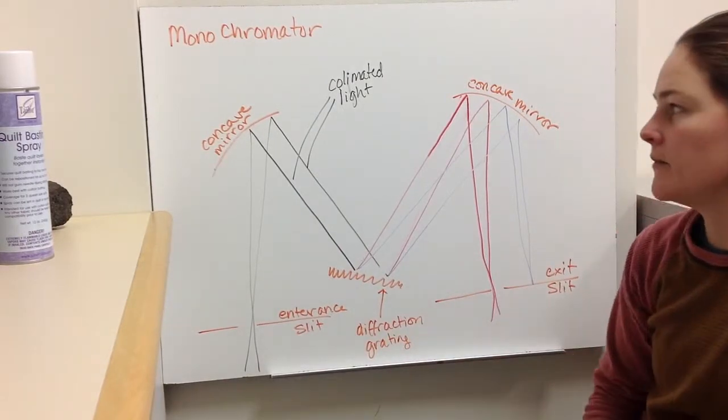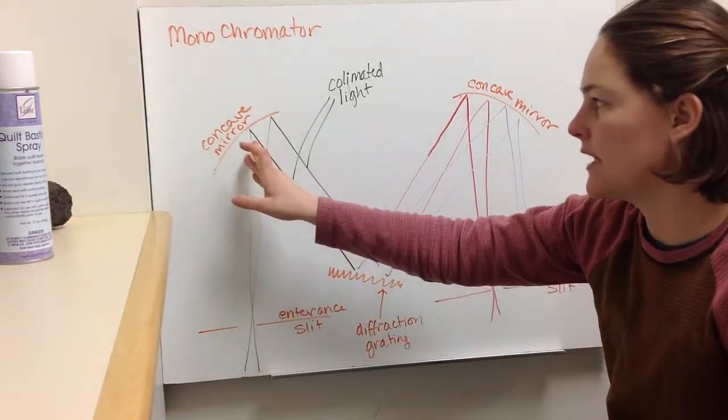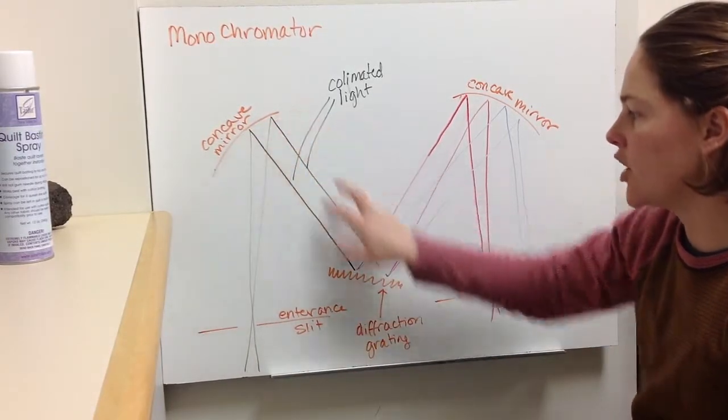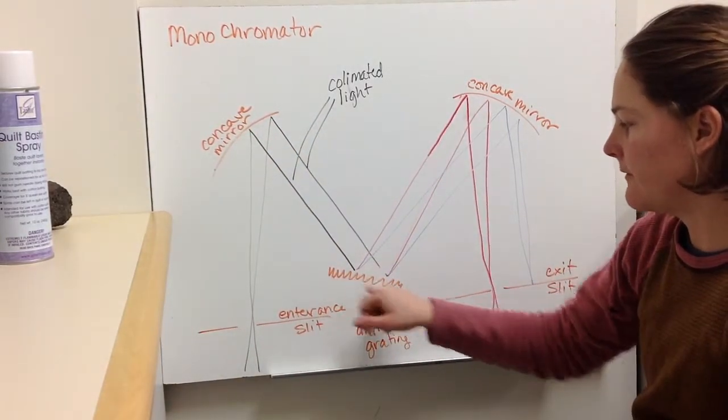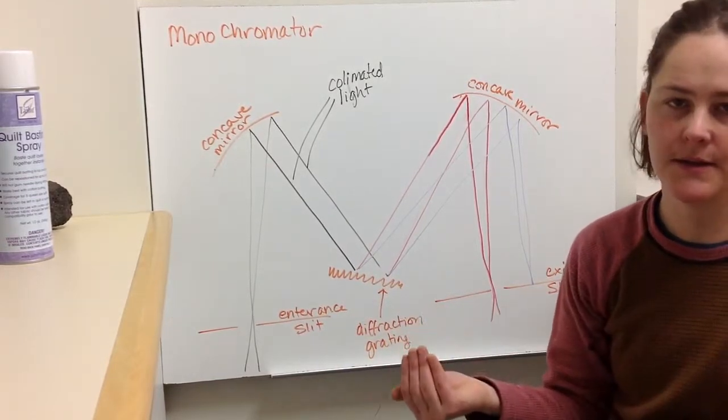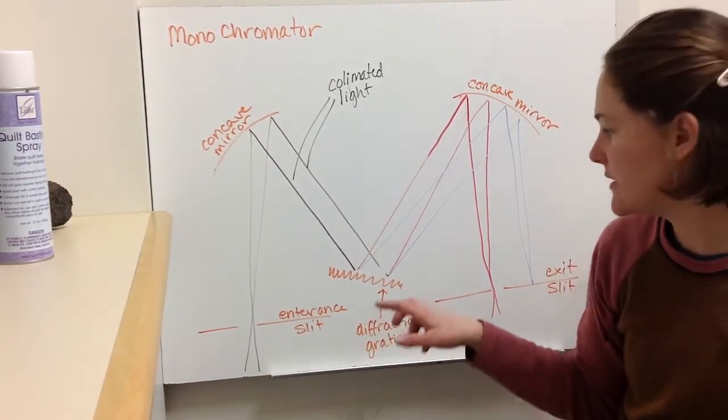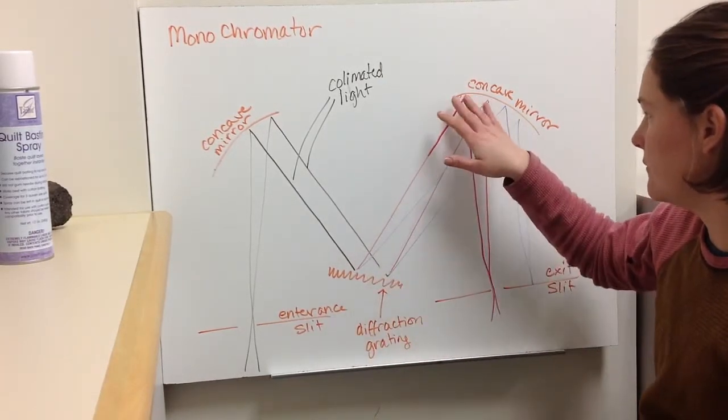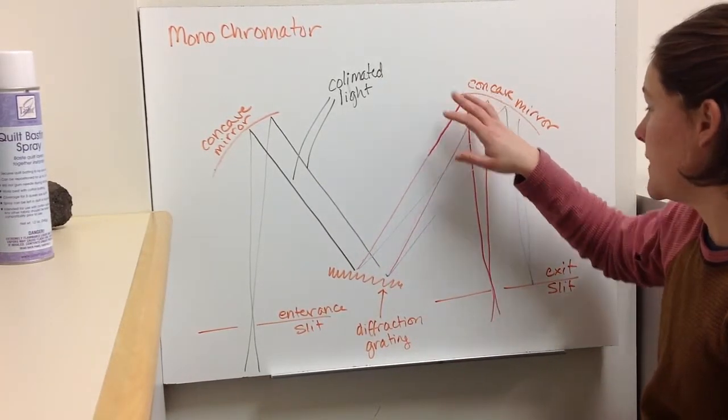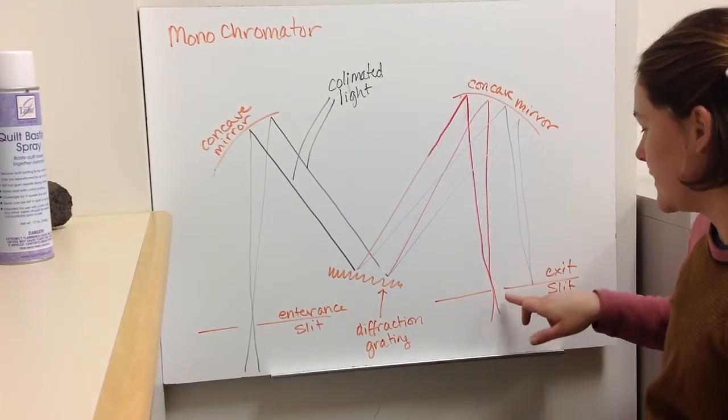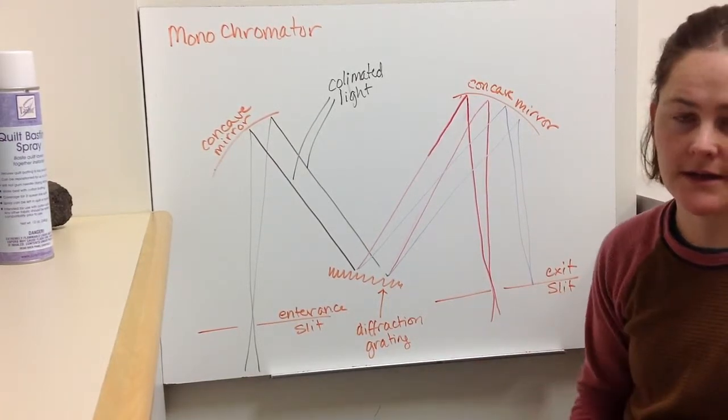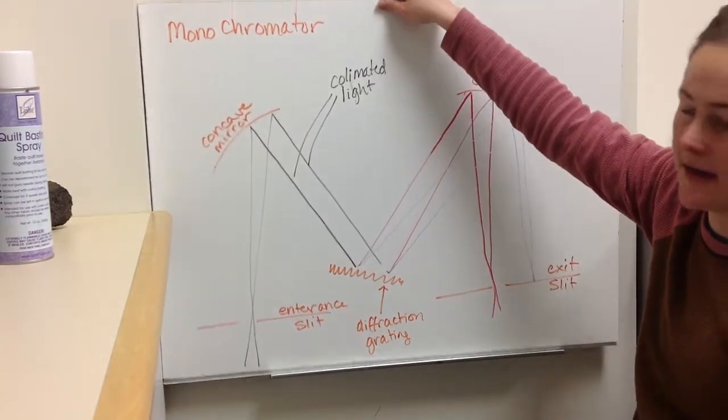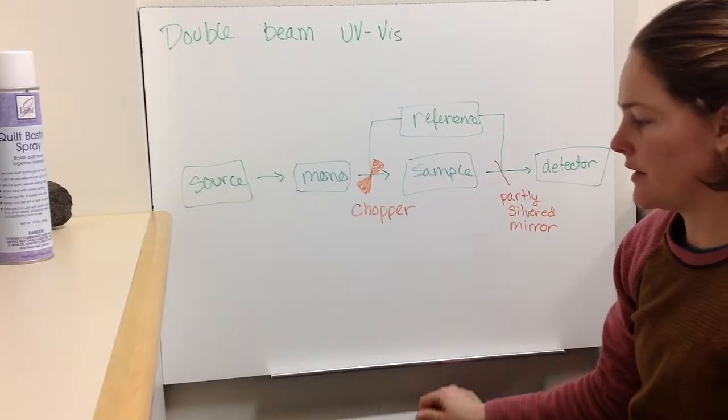So let's look in a little bit more detail at a monochromator. So you have white light coming in through the entrance slit. You're going to have a concave mirror that collimates the light, and then you're going to have a diffraction grating, which is going to break it into its component wavelengths. And then that wavelength dispersed light is going to come up and hit a second concave mirror, and that's going to focus a single wavelength down onto the exit slit. So then that one wavelength can go on through the optics.